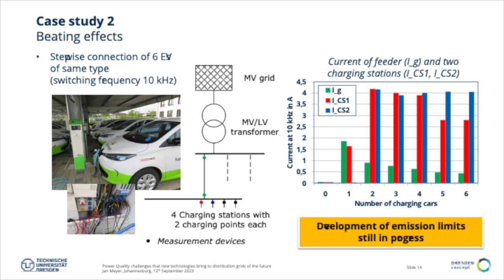What was even more interesting is, as soon as you connected the second one, you got less current flowing into the network, but a current of 4 amps flowing between the cars because of the impedance configuration. The impedance of the chargers is much lower at that frequency than that of the network. Usually I say current is like students looking for the shortest way, so it will basically flow to the other charger somehow.